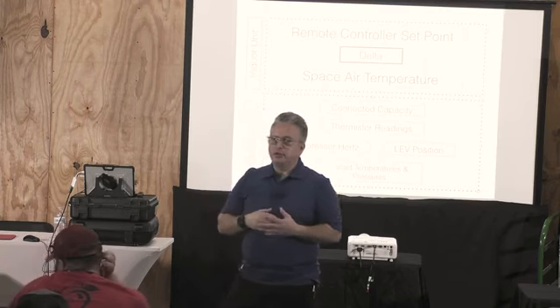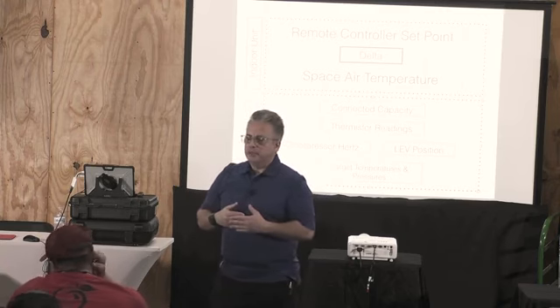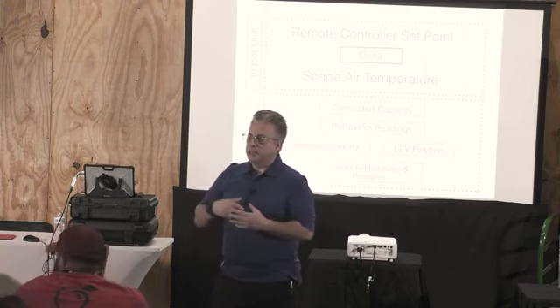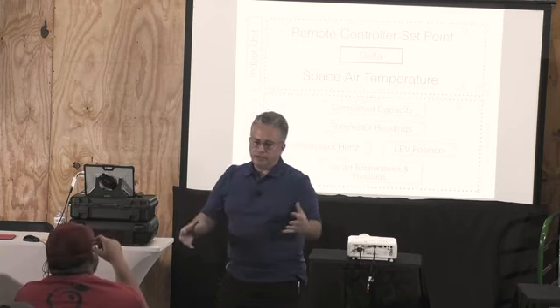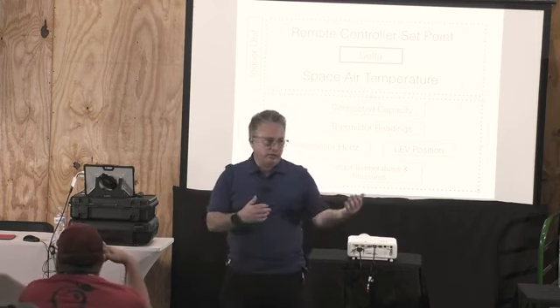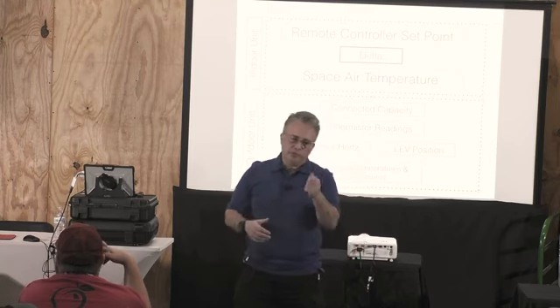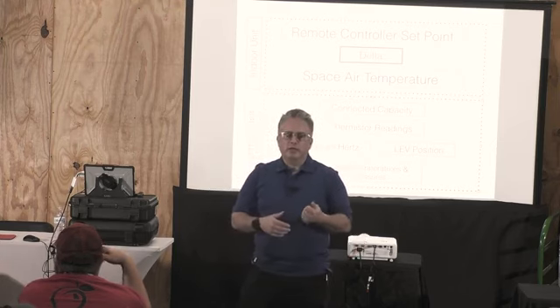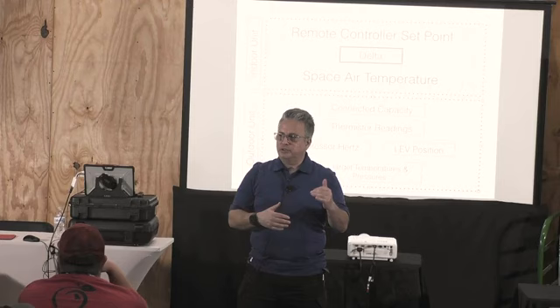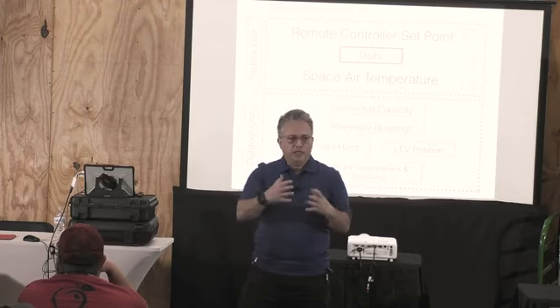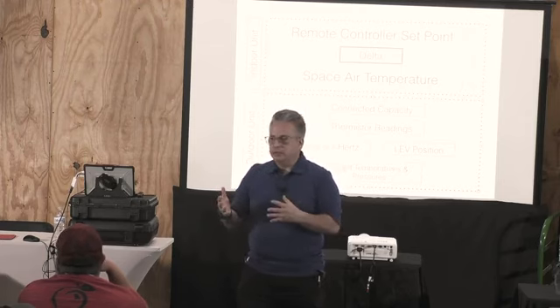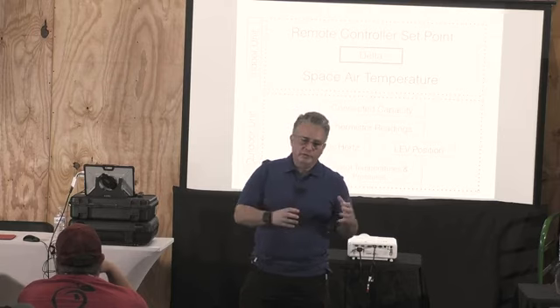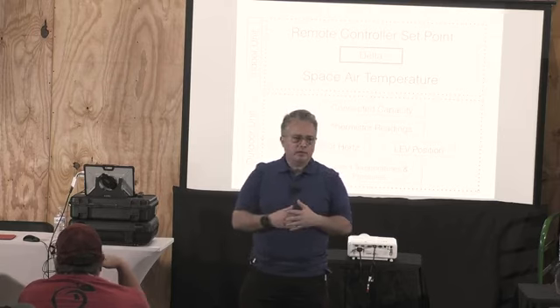So you can also coat the coils. There's an epoxy. You have to disassemble the coil and dip it, which is the proper way. If you spray it on, it's going to last maybe 2 or 3 years, so you have to come back and retreat it, which may be a maintenance contract. But if you dip it, it's going to last a lot longer.